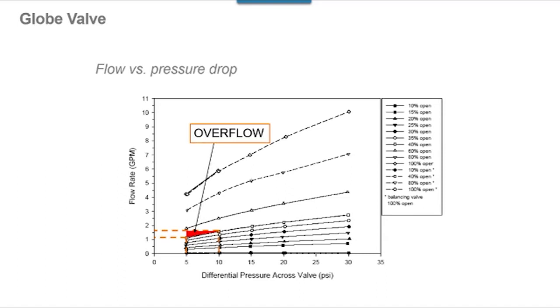have a high number of those valves, and a fourth of them were sending us an extra half gallon per minute of water. All of a sudden, you've got a lot of excess flow that you're pumping, and it's not helping the system, obviously. So this is what we're trying to eliminate by the use of pressure-independent control valves. One other point I want to make when you look at this plot is, look at each point that this valve is open. As pressure goes up, you definitely see a marked increase in flow.